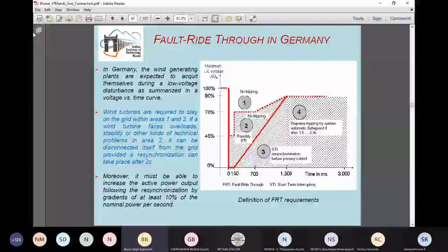This curve is saying that after 0 to 150 milliseconds, even if the voltage is 0, the system should not get disconnected. But a short-term interruption is possible. We'll discuss the short-term interruption in the coming few slides. Now you can see the thick line slowly increasing, with a ramp rate. It means even if the voltage is regained but is less than 100%, above this red thick line no tripping should be there.